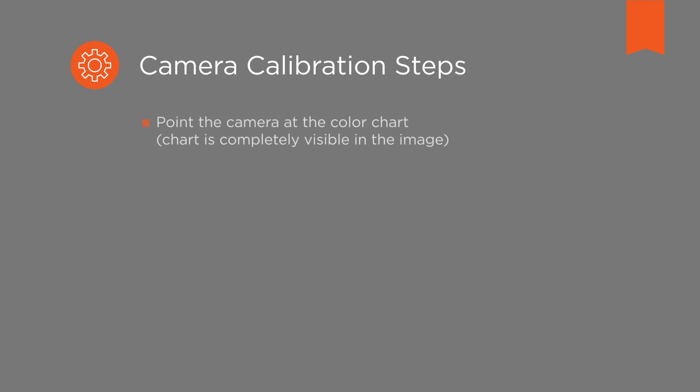Let's now have a more detailed look at how to achieve this. We are using the Basler MED ACE camera to illustrate how such a color calibration via software can work. If no suitable light source preset is available, your camera can be calibrated in just a few seconds — not hours — using the Basler color calibrator software. The first step is to point the camera at the color chart so that the chart is completely visible in the image. The software then starts to adjust the brightness to optimal levels.